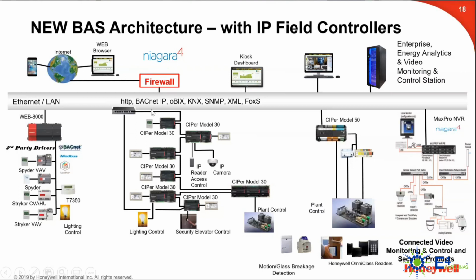The way we've historically done building automation, you can see in the left-hand column on the screen. We have an enterprise supervisor at the server layer, on the network, that pings down into a master controller. In Niagara world, we call that a JACE. Some of you may be familiar with a JACE controller. The JACE is your system network controller for all of your downstream field control devices, where your inputs and outputs happen to actually turn on a pump, turn on your chiller, turn off your chiller, etc.